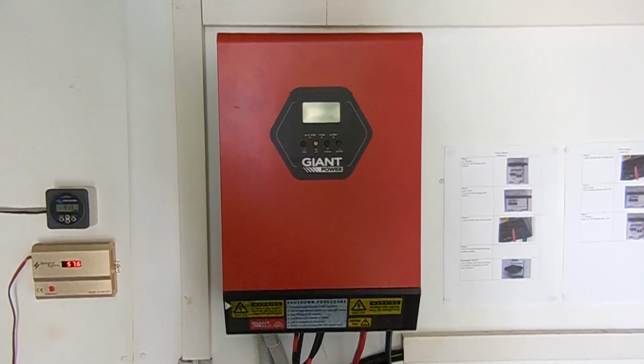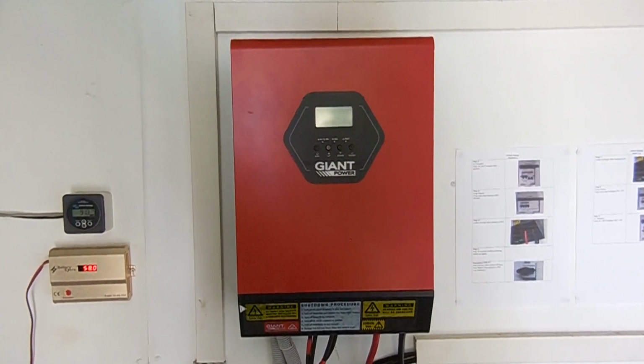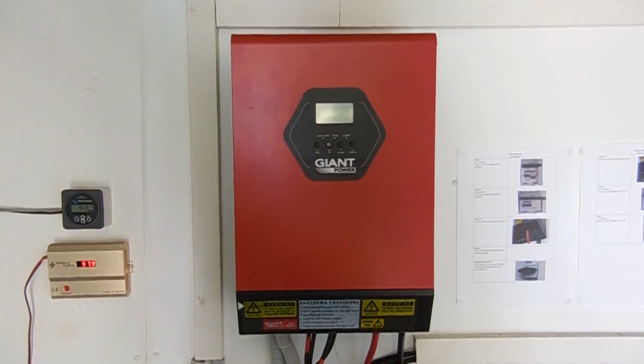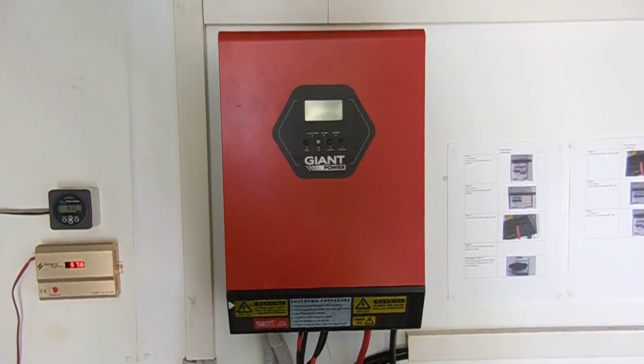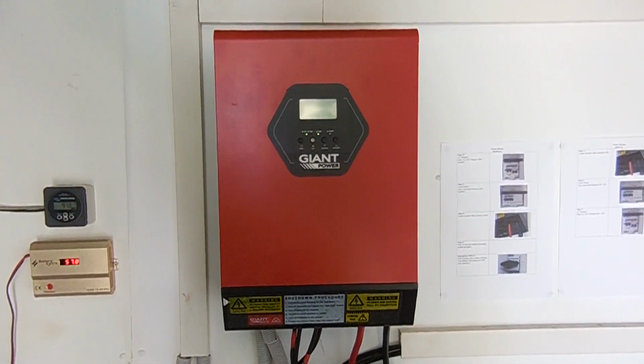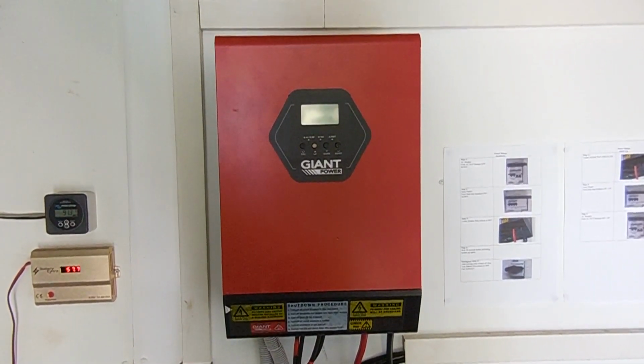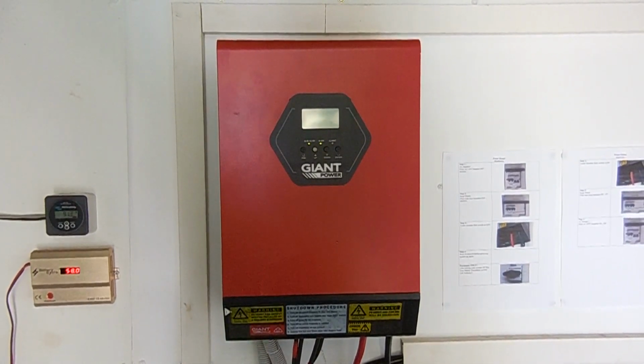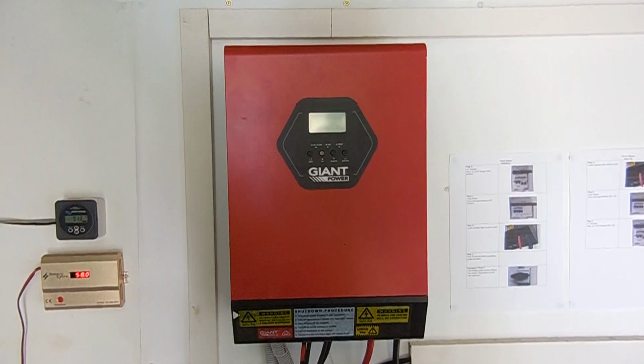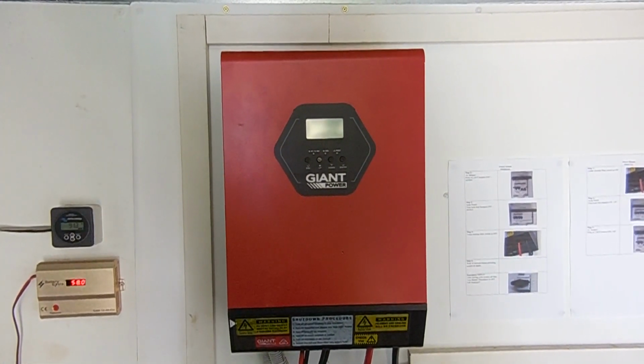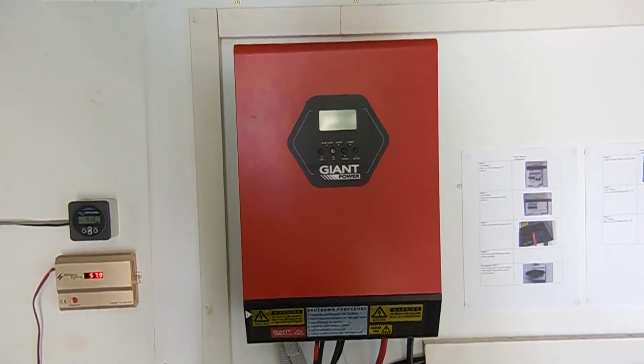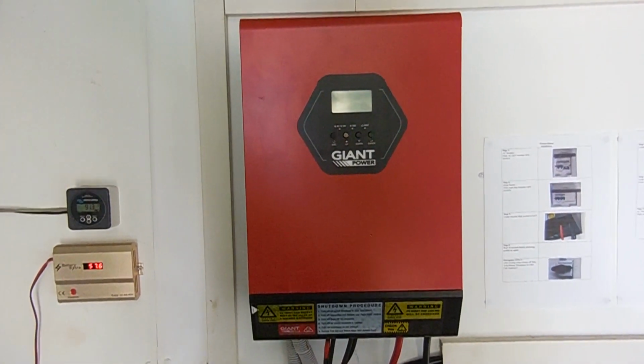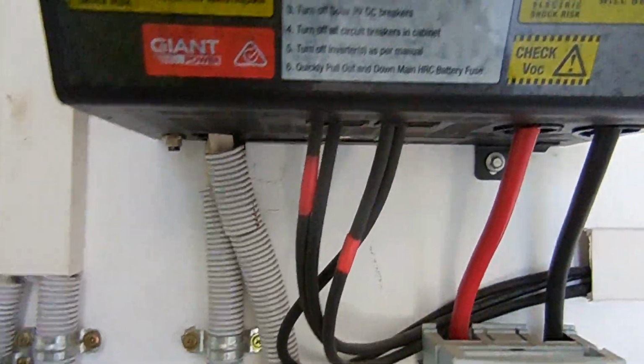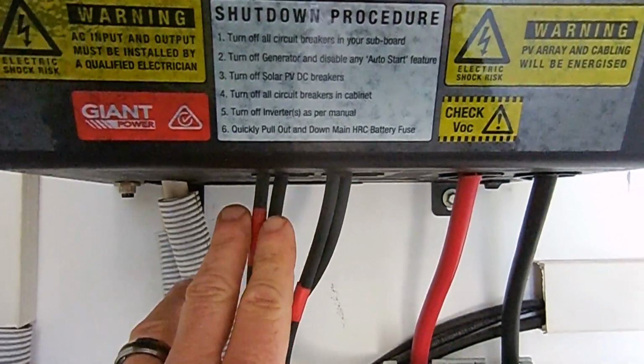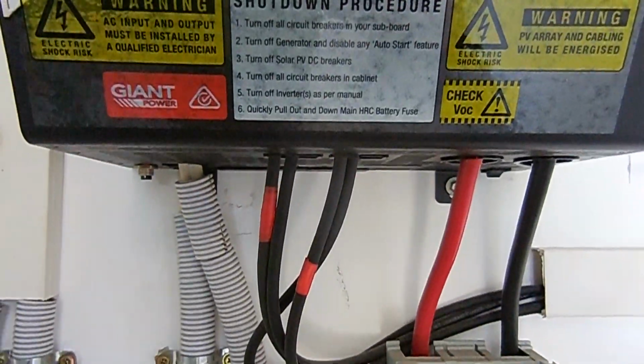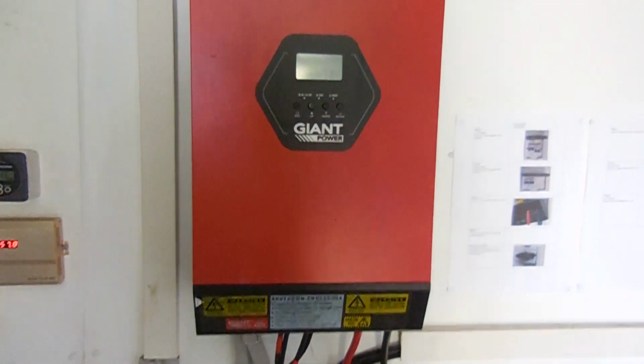This is a giant power inverter, which is a rebadged MPP solar inverter made in Thailand. So we've had this up and running now for almost 5 years with no issues. It's a 4 kilowatt inverter, 48 volt input from your battery bank. It has a built-in DC charger, so you can charge it from mains or generator, and it also has 2 solar DC regulators. That's why we've got 2 sets of DC power cables coming in here. One is from the 2 kilowatt bank of solar panels, and the other one is the 3 kilowatt bank of solar panels.